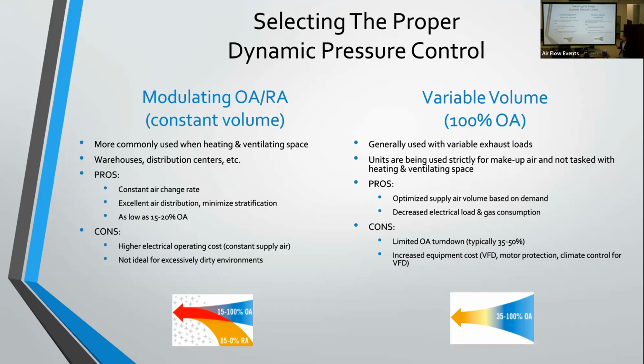So a lot of energy savings there with an outside air return air unit as far as minimum outside air amounts. Some disadvantages might be the fact that you are running the fan at a constant volume. So you're running it at its maximum air volume and brake horsepower that it was designed for that application. So unfortunately, you're not going to see any benefits of reduced electrical costs because of that. Another disadvantage might be that they're not the best applications for units or spaces that are excessively dirty. If you've got really dirty air that's being circulated back through that unit, your filters can load up quickly. You can actually cause some air balance problems if they load up too much. And you can also have some premature component failures with excessively dirty air, specifically fan bearings and the burners itself.